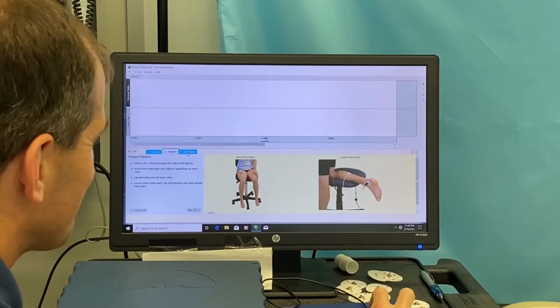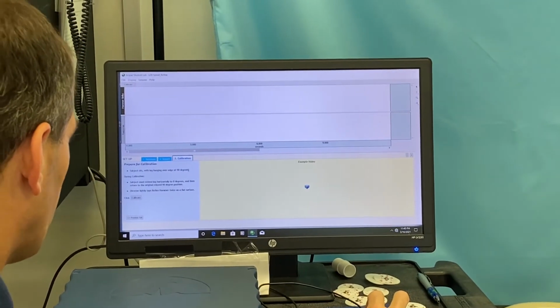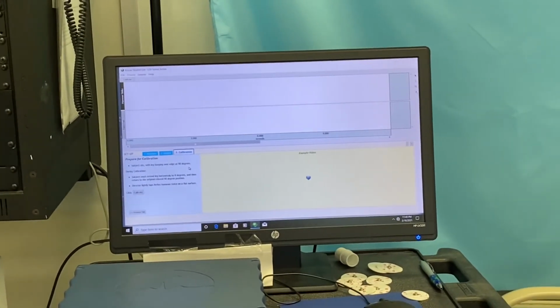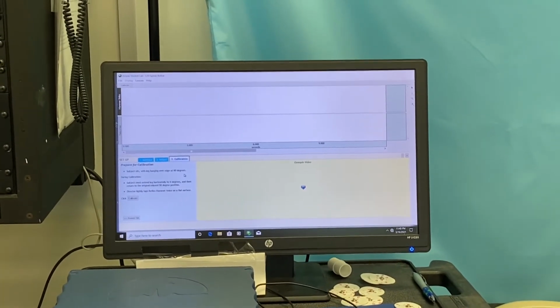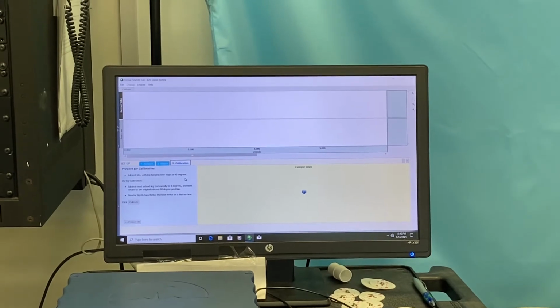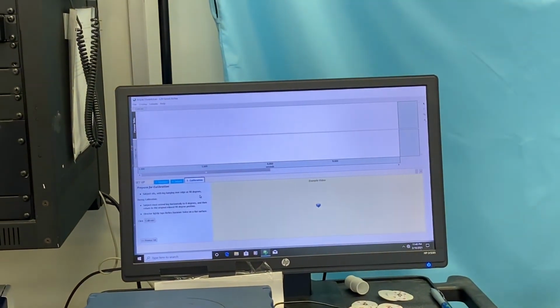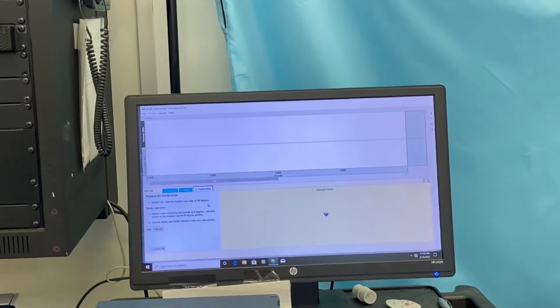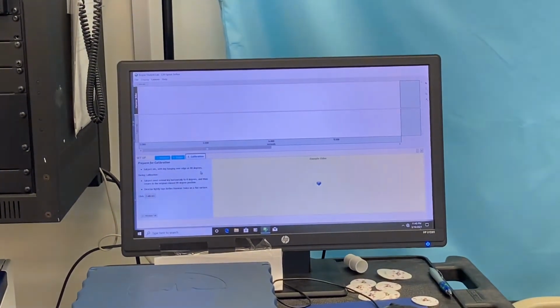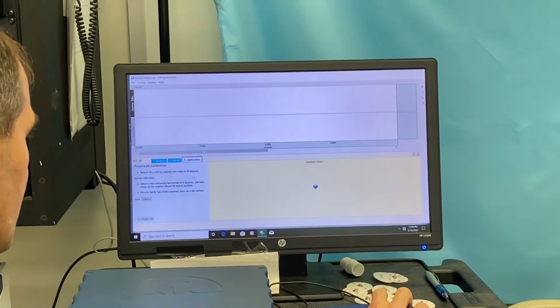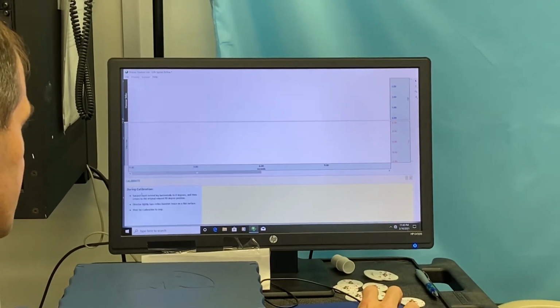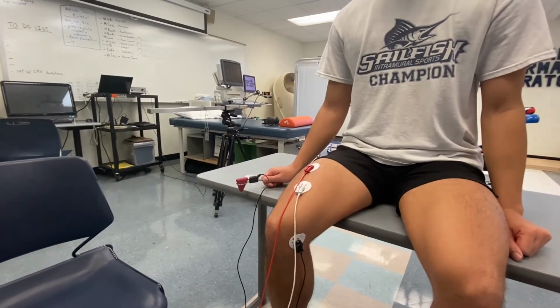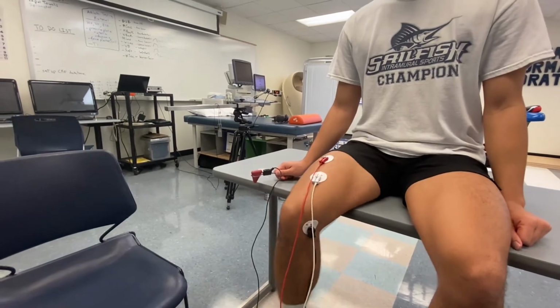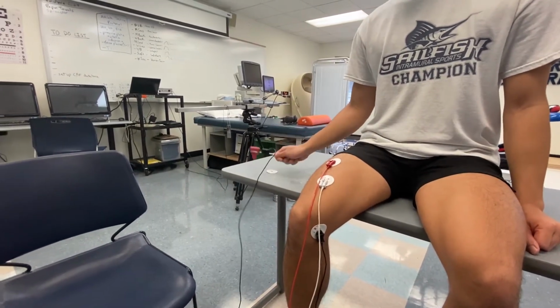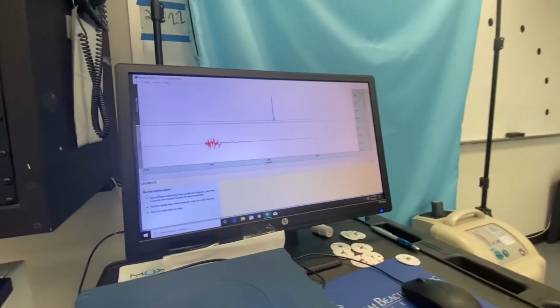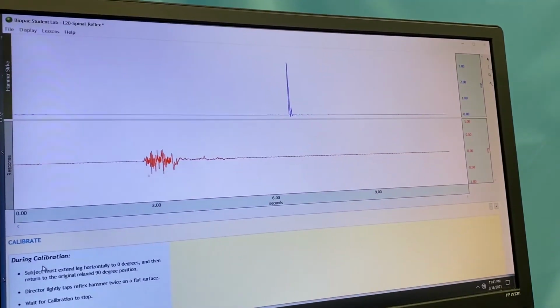So after we get our subject set up, we are going to go to calibration. And so for the calibration, when I hit calibrate, our subject is going to kick their leg to 90 degrees. That's going to give us a good contraction of the quadricep muscle. And then we're going to hit the reflex hammer against a flat surface. And so it'll look like this after we hit calibrate. So we'll ask our subject to kick their leg and then hit the reflex hammer on the table. And that'll calibrate our system on the screen.